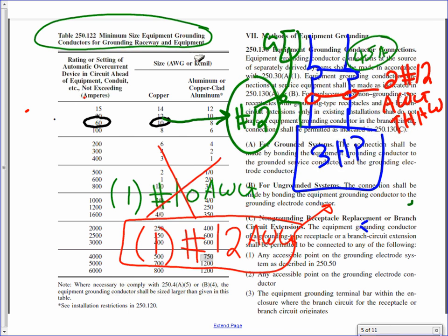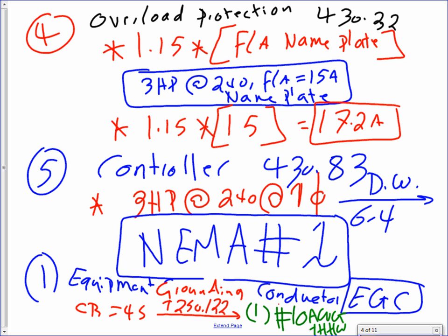So, long story short, so I don't confuse you more. I'm going to go across this, and I'm going to say the size would be what? One conductor, number what? 12 AWG THHW. Why? Because I do not need to go larger than the ungrounded conductor. Any questions, guys? Any questions? That's it. So we sized 5 things for this system, including the equipment grounding conductor.